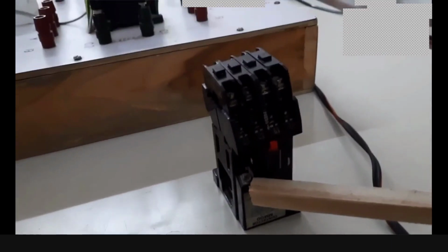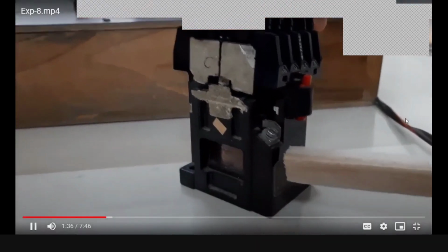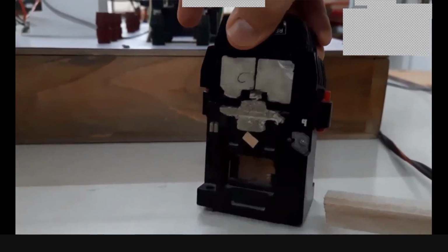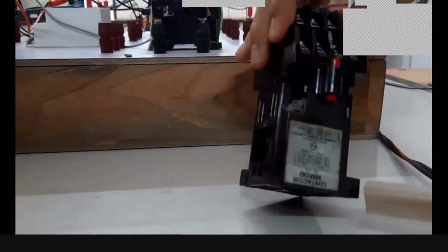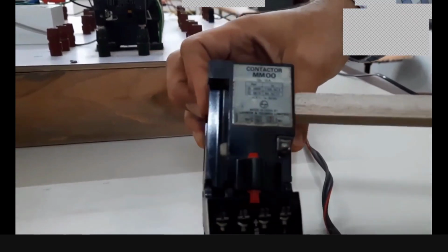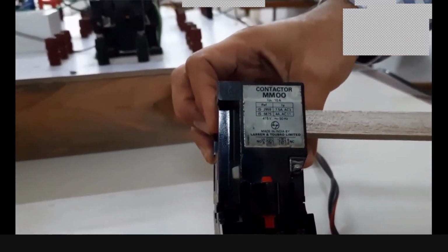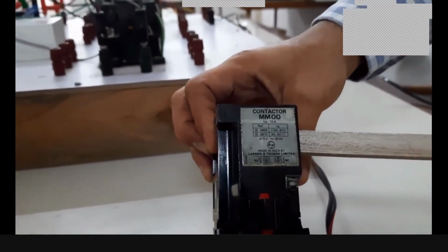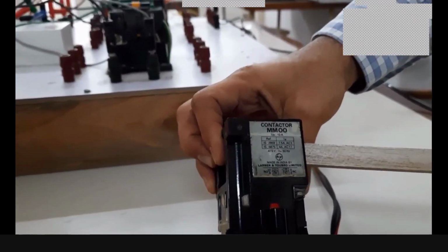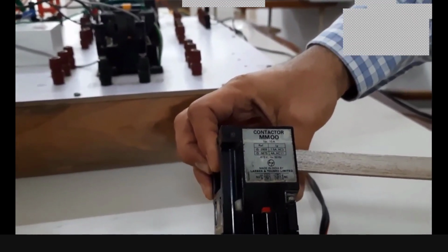On the side of the contactor, where I am pointing, this is the coil. This is the terminal of the coil. This is the first terminal, and on the opposite side there is another terminal of the coil. So there are two terminals of a coil. A coil is single for all three phases. If you see the nameplate of this contactor, the rating is mentioned over here. It is a 415 volt contactor in this case. So it's a motor contactor.